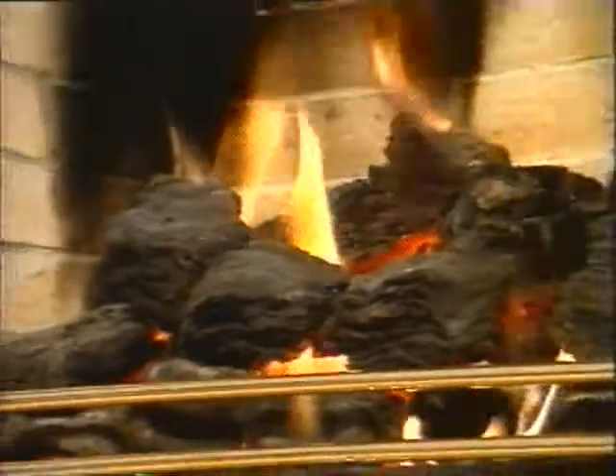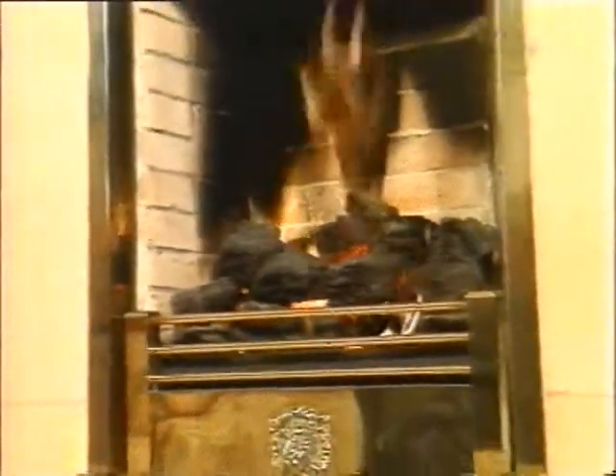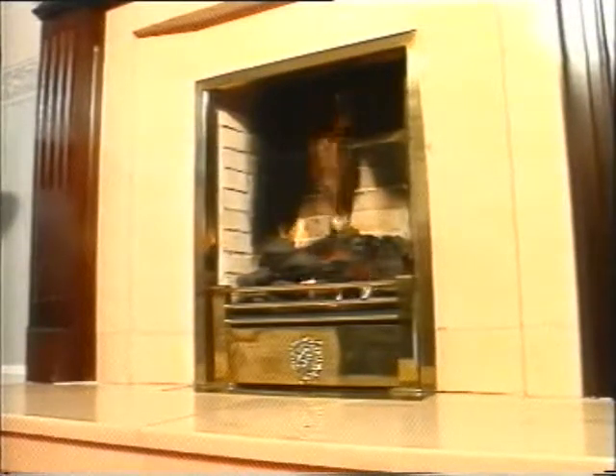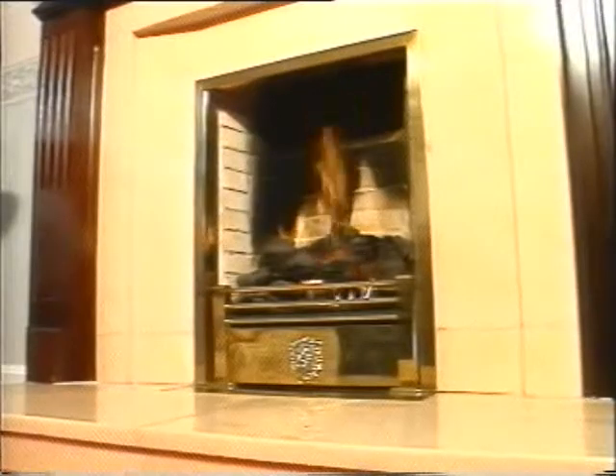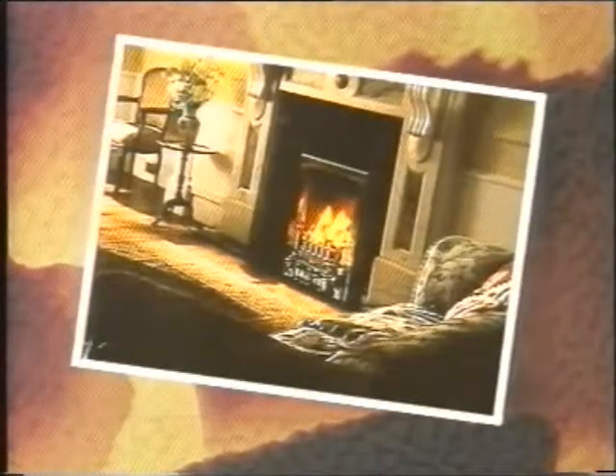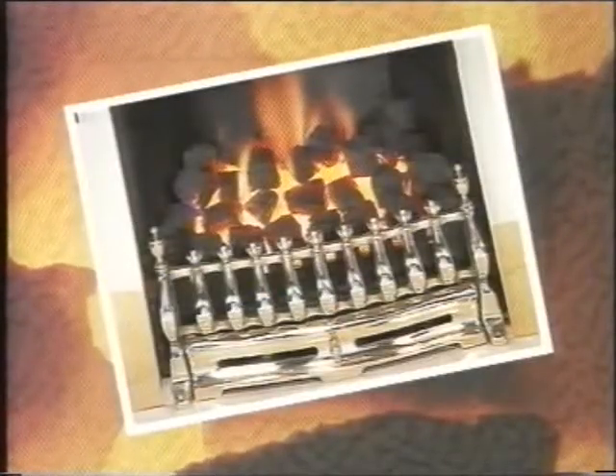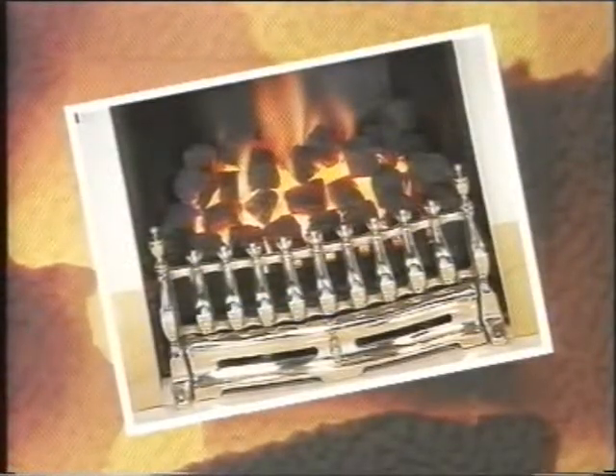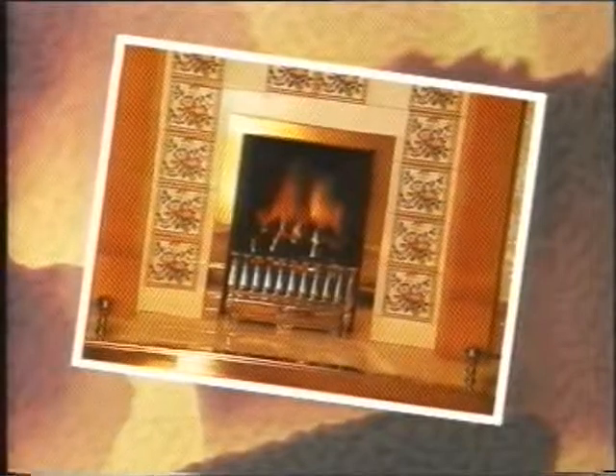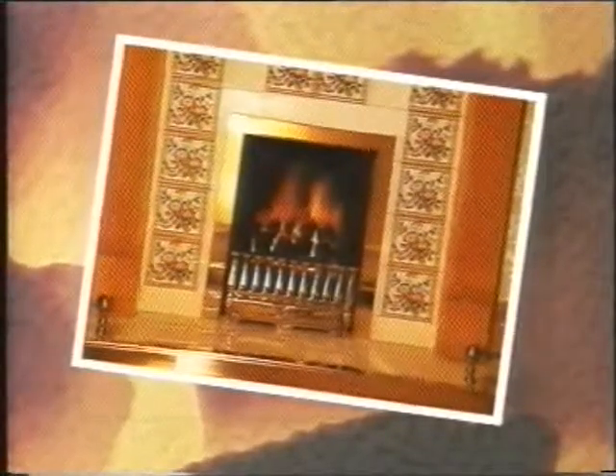The final appliance in the program is the DFE, Decorative Fuel Effect fire. You can see from its open construction that a Class 1 flue is required. The rules about siting, hearths, catchments and so on are all exactly the same as those for ILFEs. The only additional point is that the fireplace recess must have a smooth gather to help the flue system to work effectively.